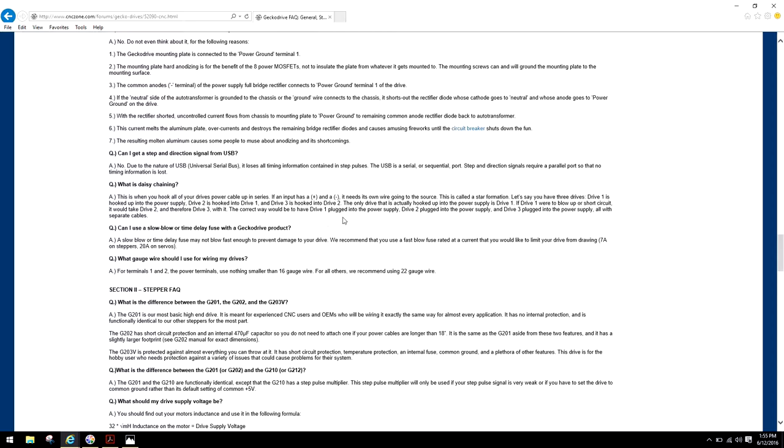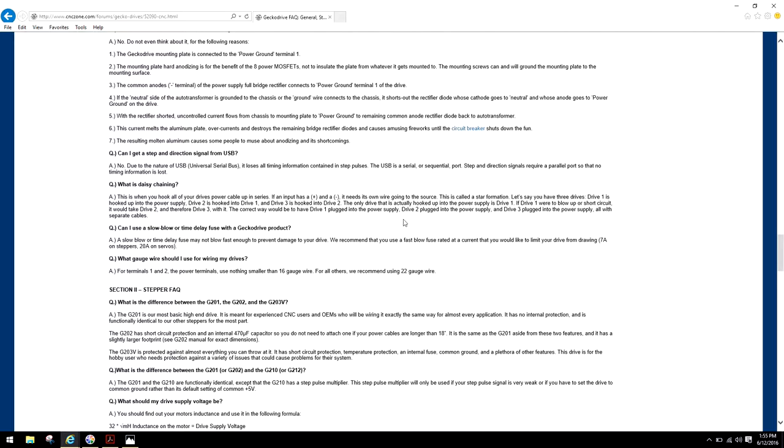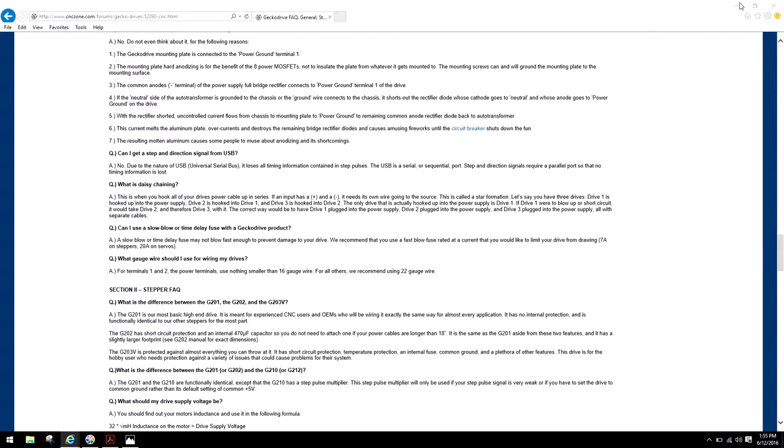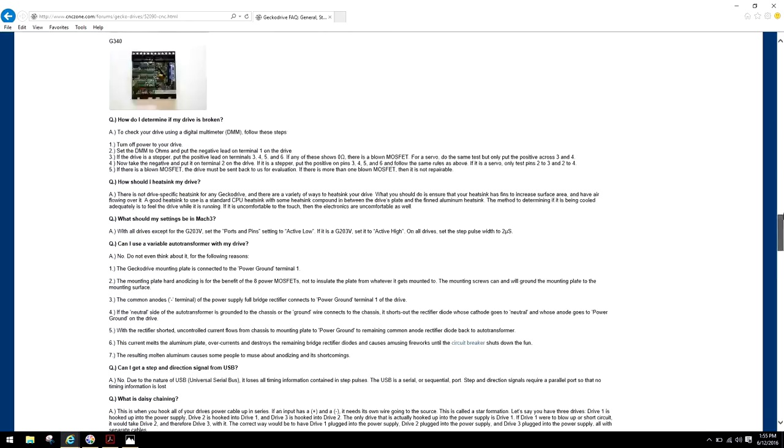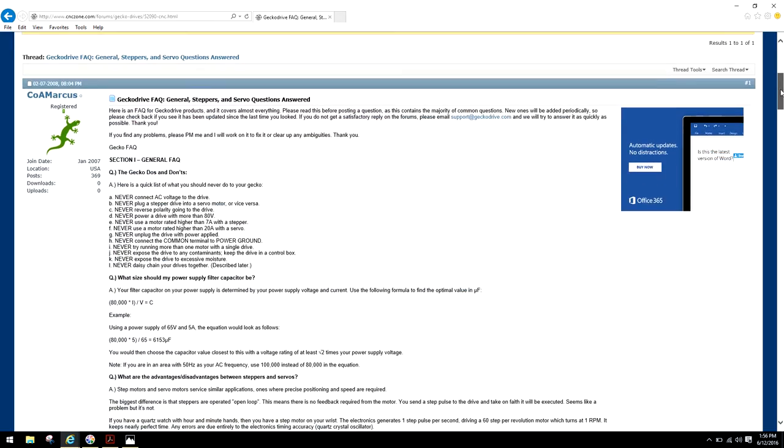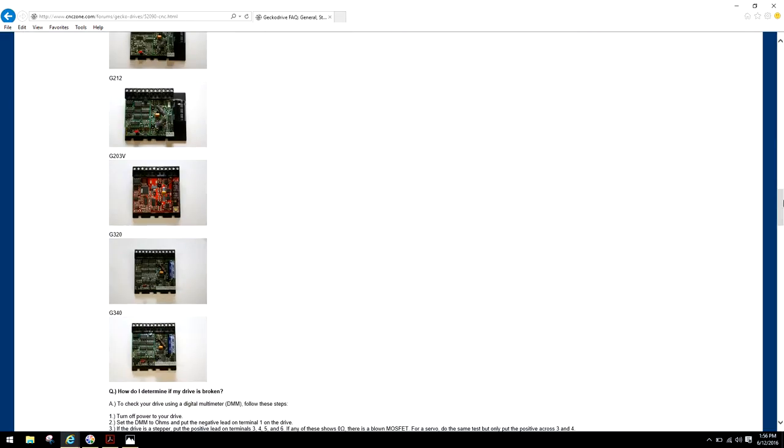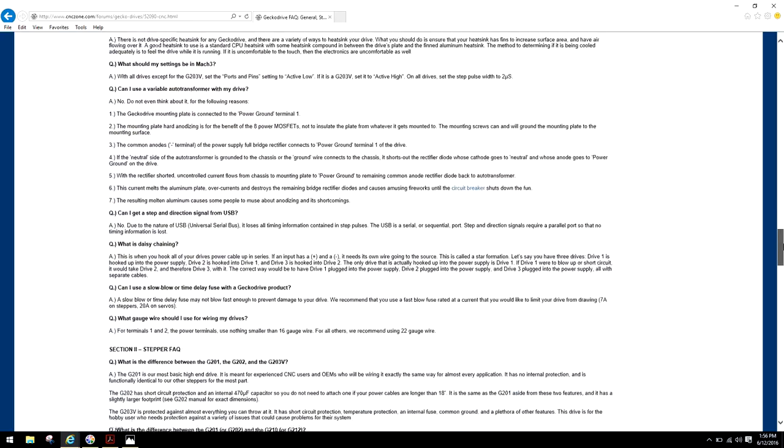Do it right the first time. Yes, you're saving some time because you're just running a jumper wire over. In the long run, it'll bite you because what you'll find is that it causes more time and effort trying to find what blew up, and it can also blow other drives. So think in that aspect and be very cautious with it. Now I'm going to read direct from them. The correct way would have been to have drive one, drive two, and drive three all plugged into the power supply with separate cables. This is direct from Gecko, from Marcus, lead engineer.